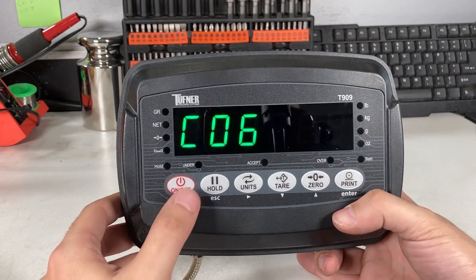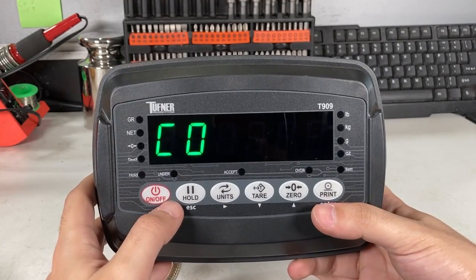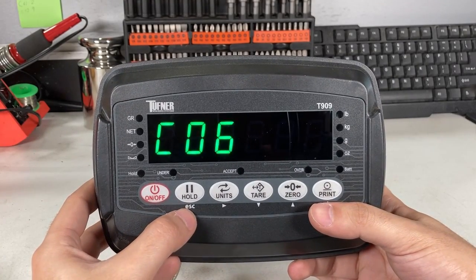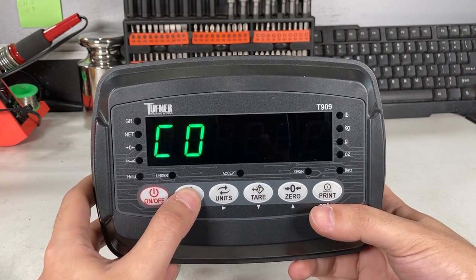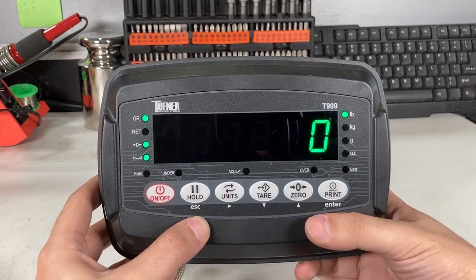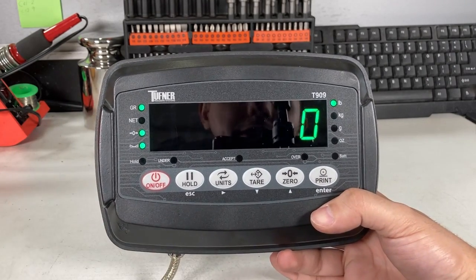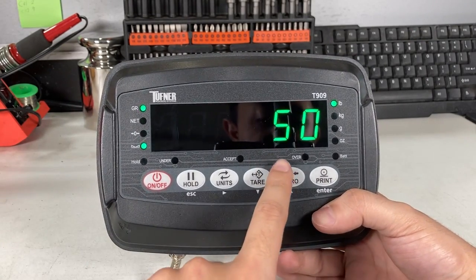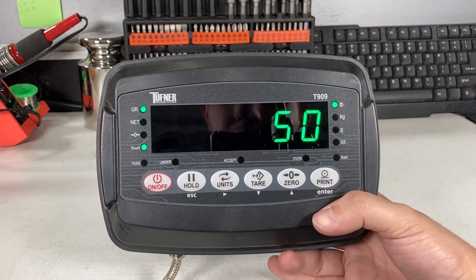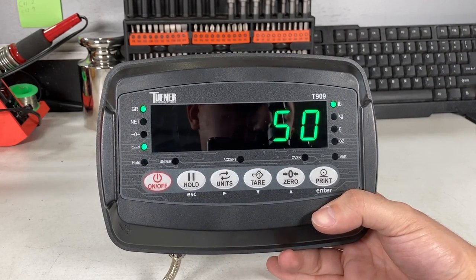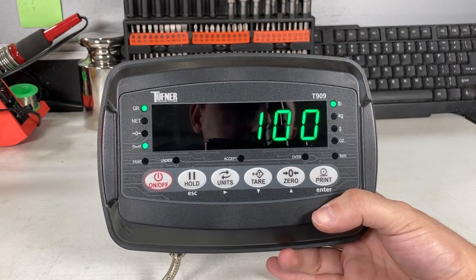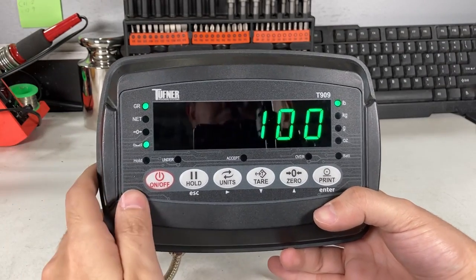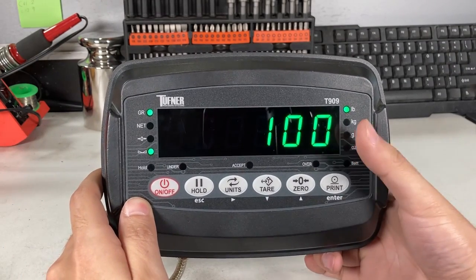Press print. You'll see C06. So now you're at C06. To escape, you see the ESC to save and exit from the menu. Now I'm back at 0. So now when I put my weight on there, you see 50 pounds shows up because that's my correct weight. So that's how you connect it. And if I add another 50 pounds, you'll see 100 pounds. It's 1 pound accurate. So that's how you calibrate the T909.